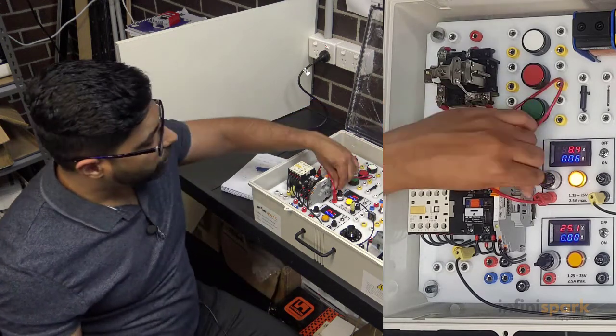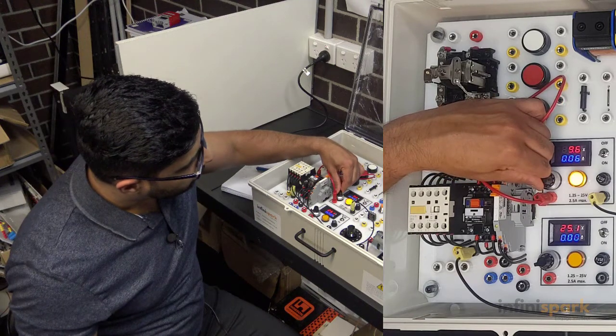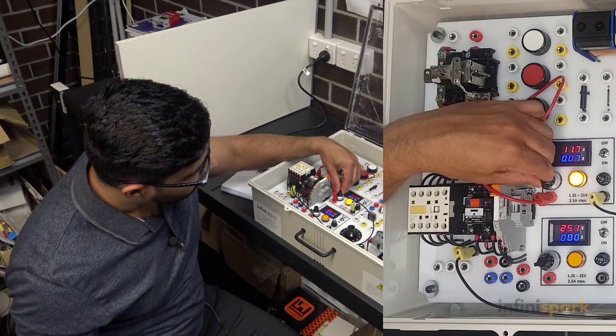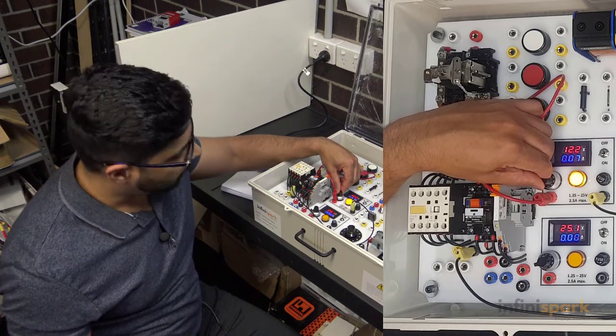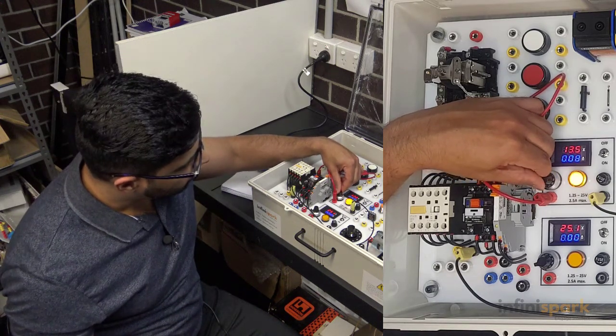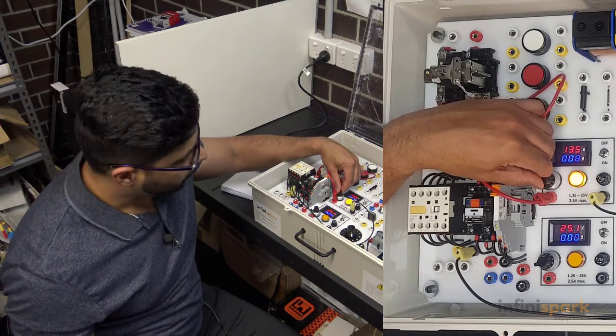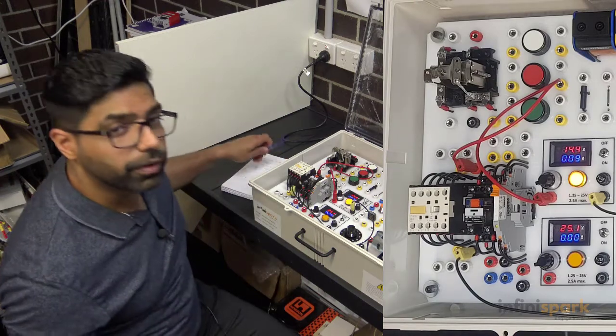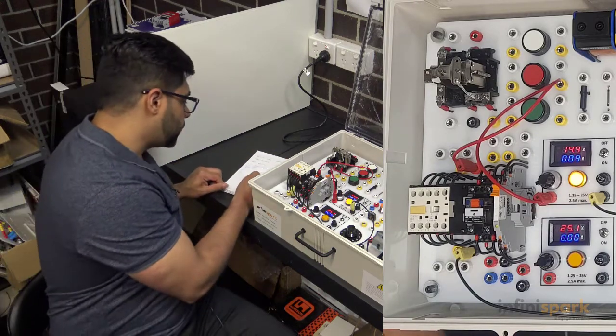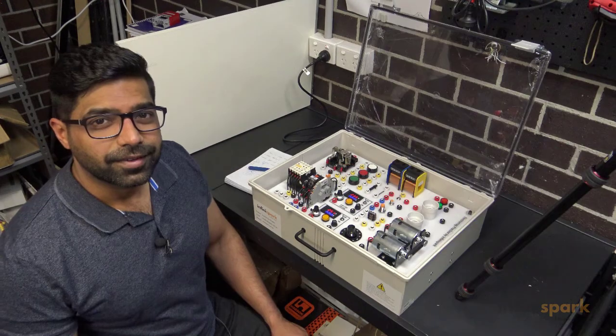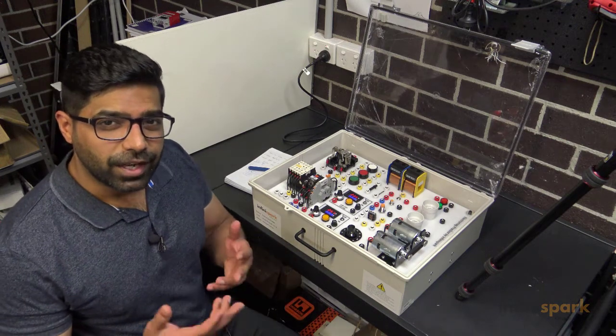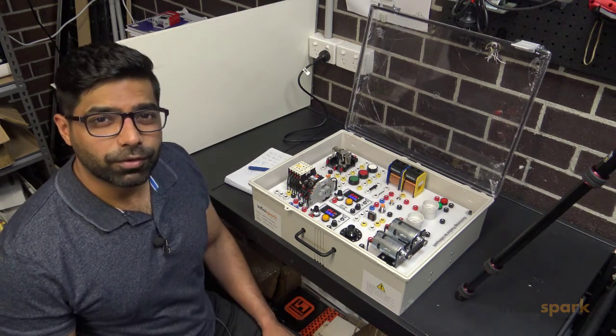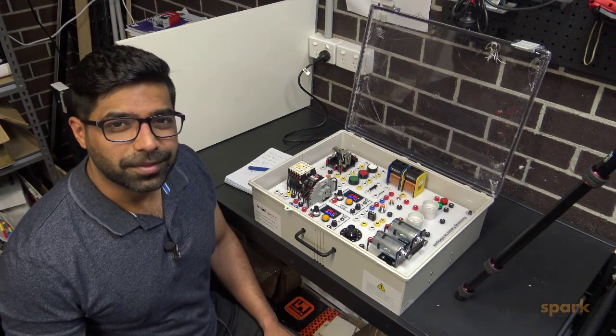At 8 volts nothing, at 10 volts still nothing, 12 volts still nothing, 13 nothing. At 14 volts or 14.4 volts the contactor pulls in. I hope all this made sense. If you found this video useful please like it, and if you want regular updates of my videos please subscribe. Thanks for watching.